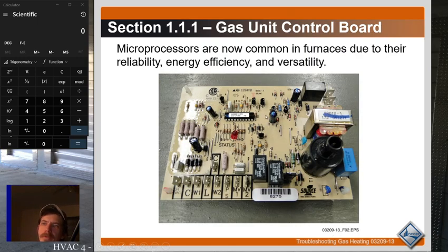You pretty much always have a circuit board on gas furnaces these days, because using regular controls and relays to verify the sequence of operation for gas equipment is relatively complicated. It's way easier to do with a microprocessor, so most gas equipment is going to actually have a circuit board now. Older equipment didn't have it. There are ways to do every step in that sequence without a circuit board, but it's way more complicated than just using a circuit board.